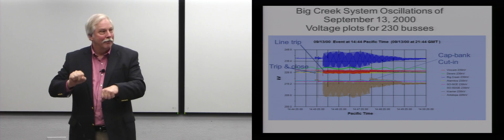Synchrophasors allow us to detect that. The schemes to detect and remediate these are called remedial action schemes. This is one being developed right now by Southern California Edison, spanning the entire southern portion of California. The scheme is pretty straightforward: on the left-hand side are monitoring devices that monitor the status of power lines, open and closed, and whether they are overloaded. This information goes to a logic processor, which does basic logic that says if this line's overloaded, and this line is overloaded, and this line trips out, take action. The action right now is shedding load, and these are the mitigation devices connected to the distribution feeders that go and shed load.